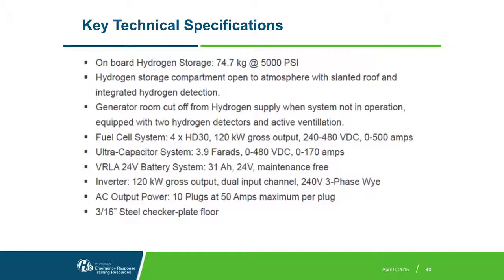The generator room, which has all of the electronics and so forth, is cut off from the hydrogen supply when the system is not in operation, and is additionally equipped with 2 hydrogen detectors. So should there be a leak, you would be able to detect that, and the appropriate measures would be taken by the system. That generator room includes the fuel cell system, the ultracapacitor, battery systems with the inverter, and then we have 10 output plugs, and they cite this steel floor as another technical spec.